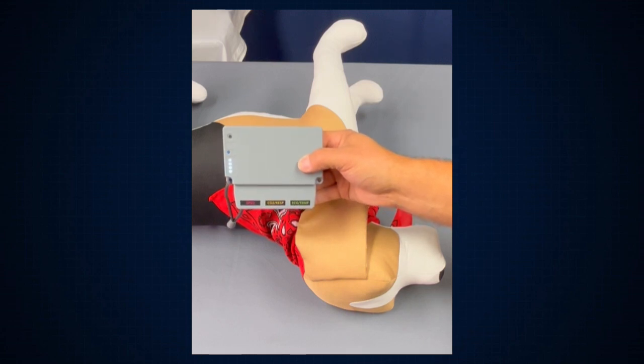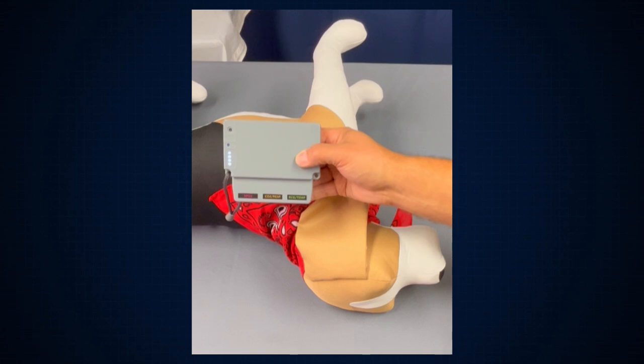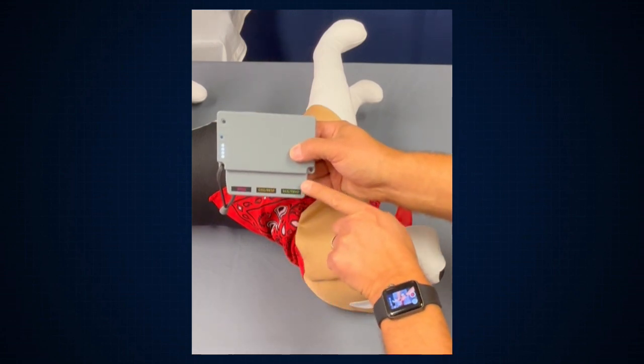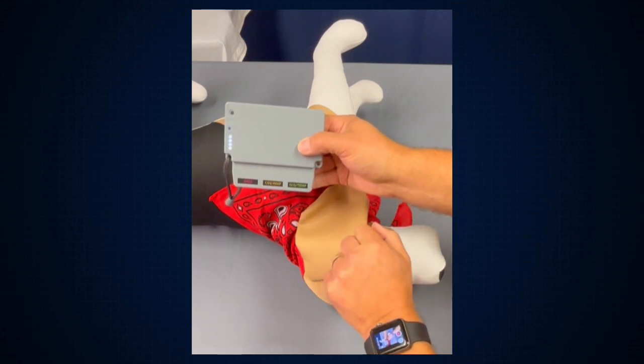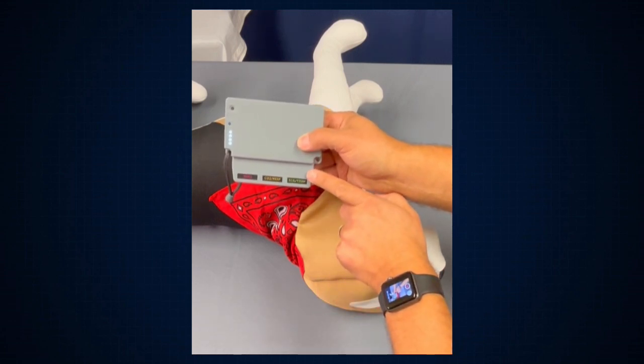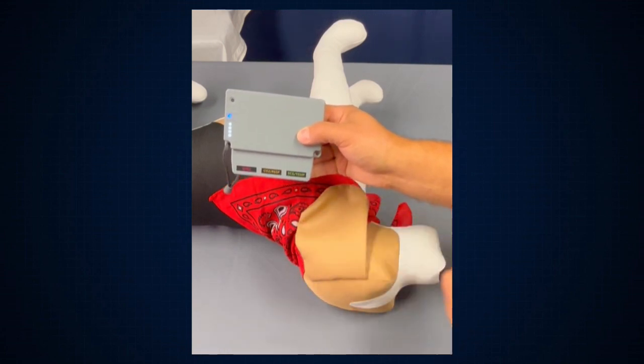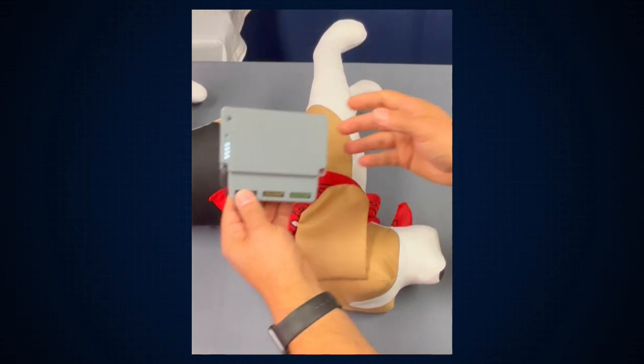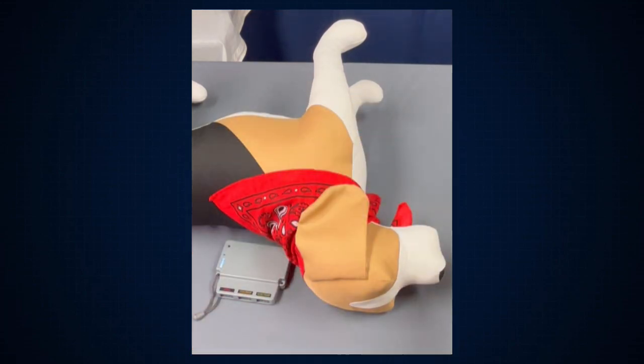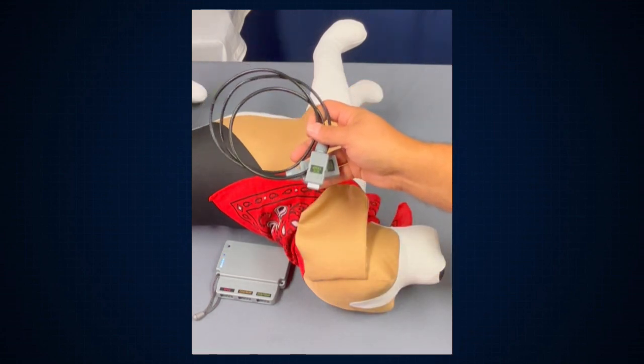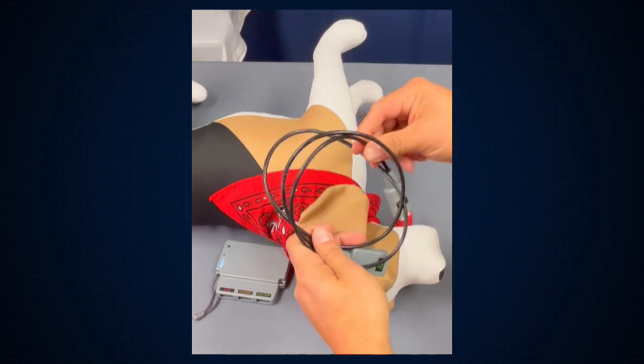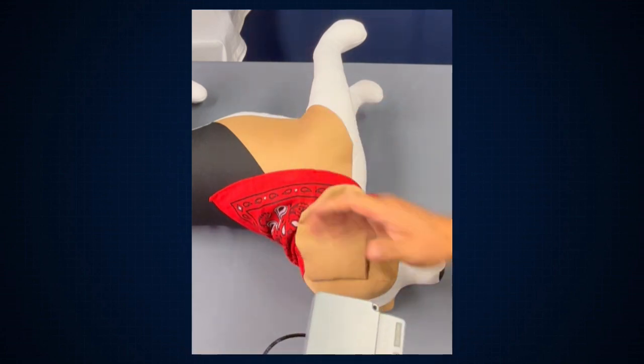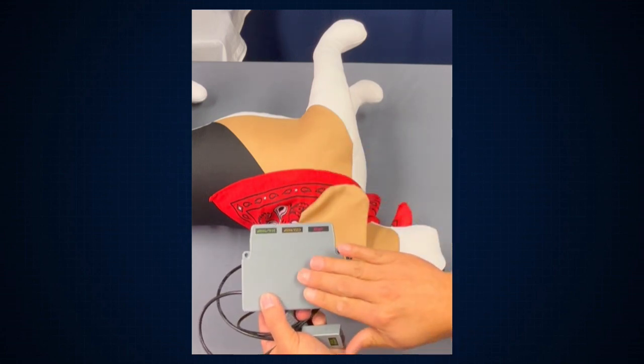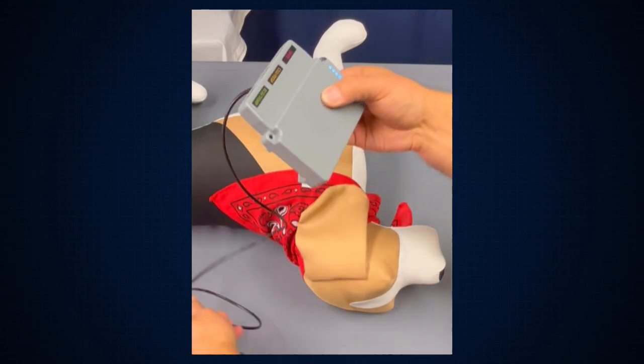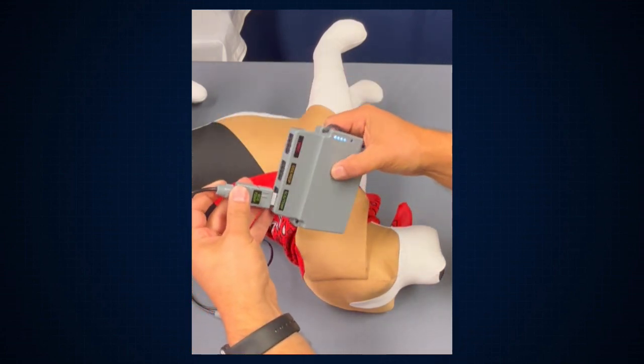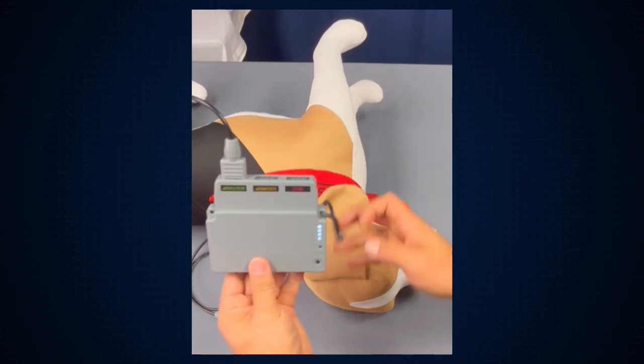It's very important. Now that we have the wireless main module on, you can either choose to go leads directly into the esophageal, the ECG temperature port. You can use esophageal probes or either of the two lead wire ECG sets. You can plug directly into the port with those items, or you can use the ECG temp extension cable. I'm going to go ahead and grab that item. The ECG temperature extension cable is definitely optional. You do not have to use it. It certainly does help if you are needing extra length from the connection to the patient, away from the module itself. To use the ECG temperature extension, just simply plug the extension cable directly into the ECG temperature port, and then you are good to go.